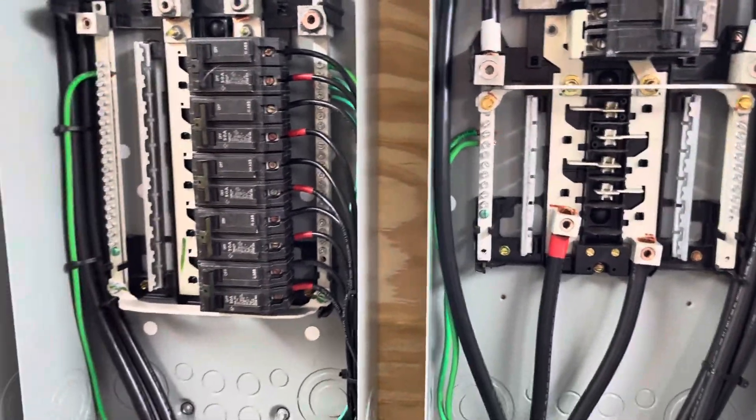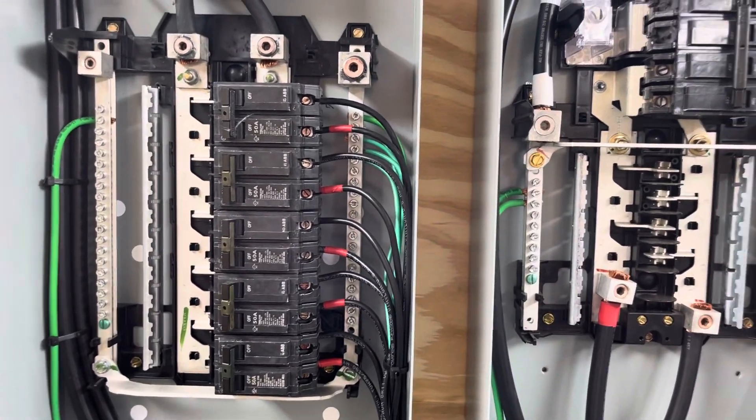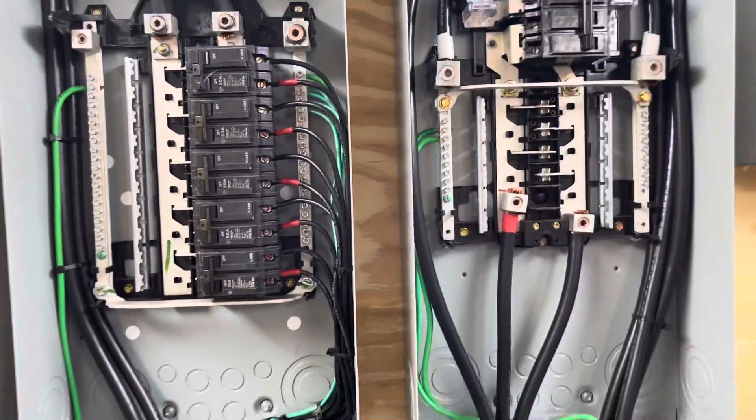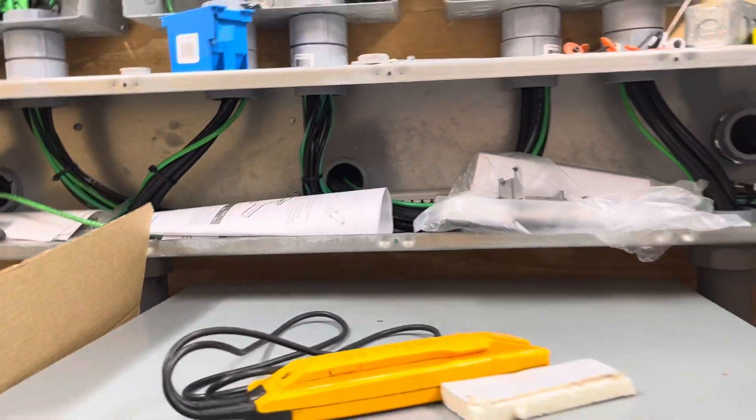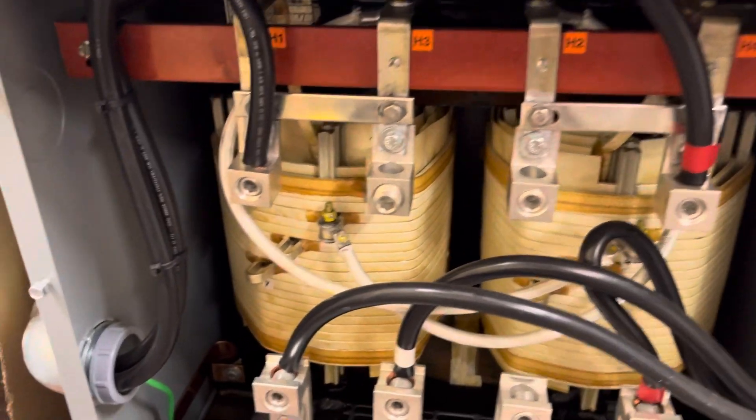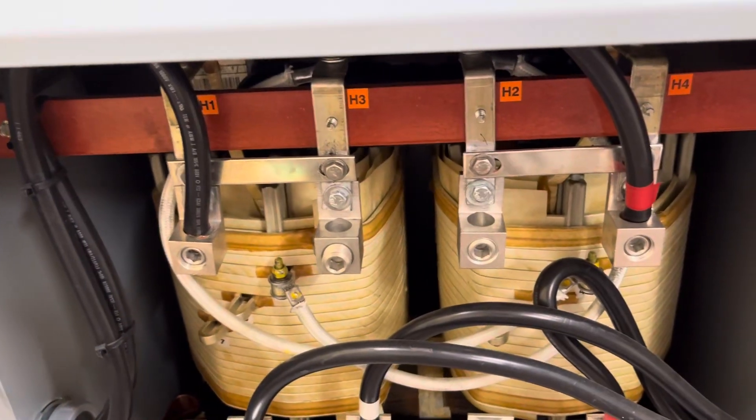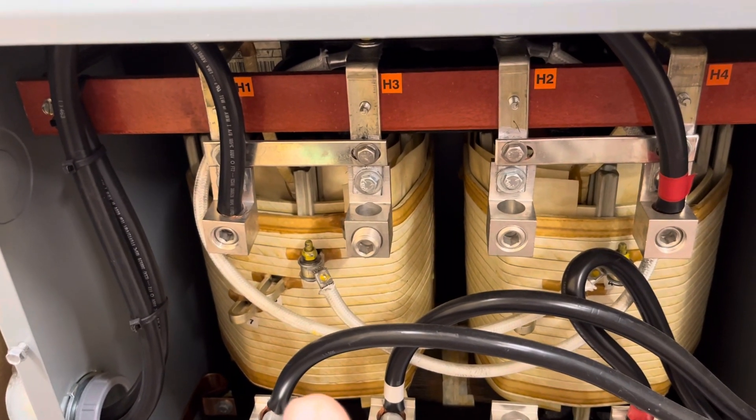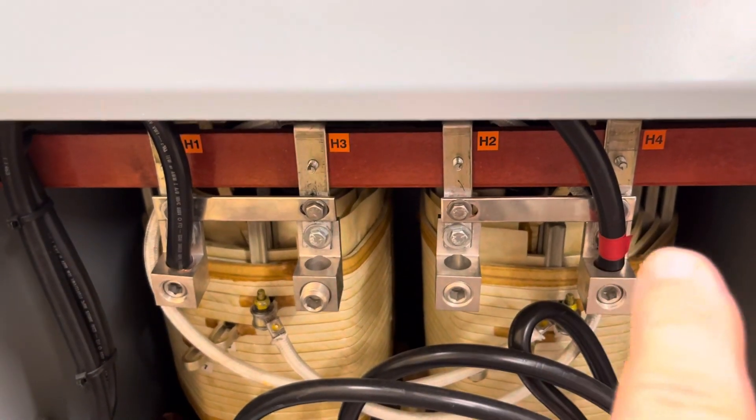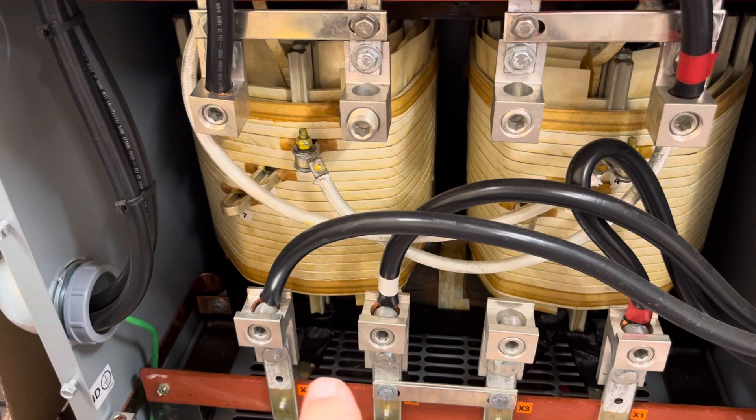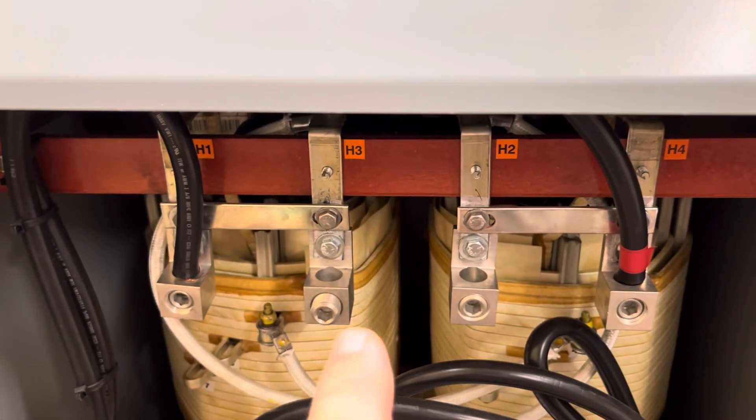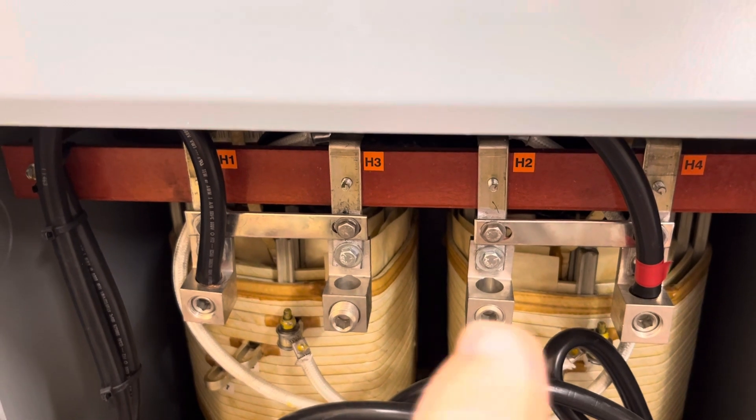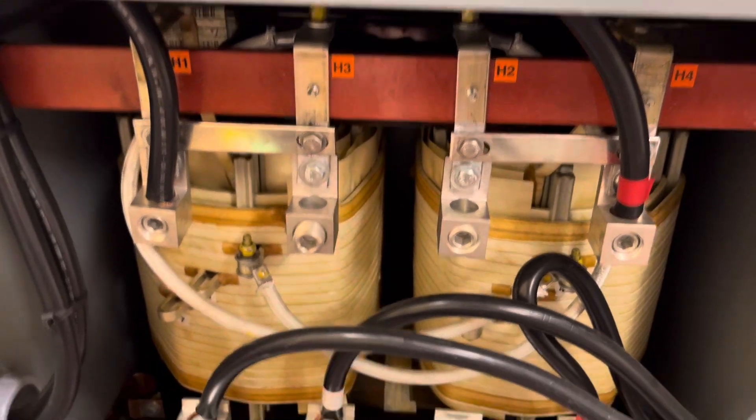Now, the auto transformer is a different type of transformer. And most of the ones that you see on YouTube are little 5KVA transformers. But in essence, what they are is a single set of windings of a transformer. This has two sets, the primary set and the secondary set. In an auto transformer, you only have a primary set. Now basically what you're doing, this would stay in series.